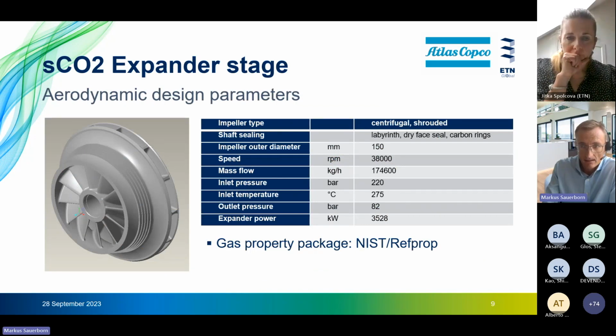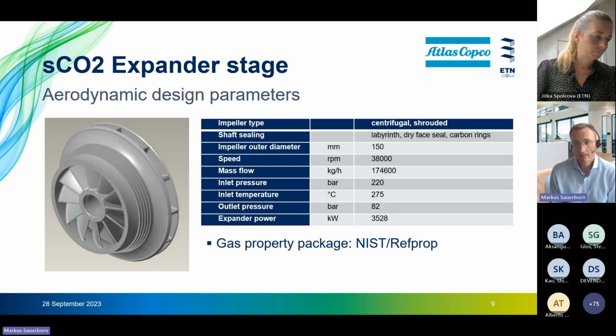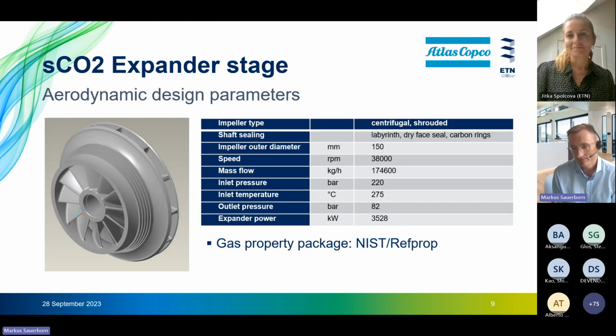Here on the next slide, an overview of the main aerodynamic parameters of the expander stage. The expander is a radial inflow type design. By the way, the radial inflow expander was invented by Carl von Linde at our present location in the last century, just as a side note. And the impeller we have here is a shrouded design with an outer diameter of 150 millimeters and an inlet blade height of less than 10 millimeters, which is rotating at 38,000 RPM.